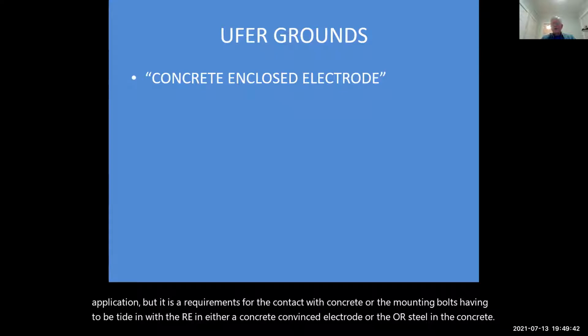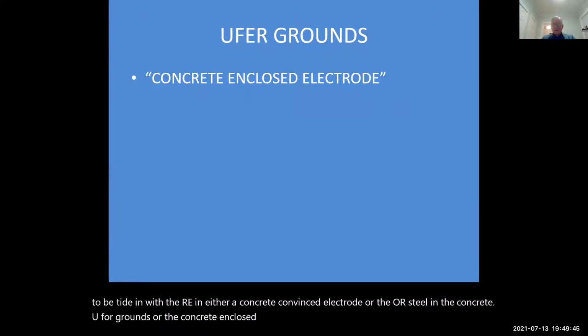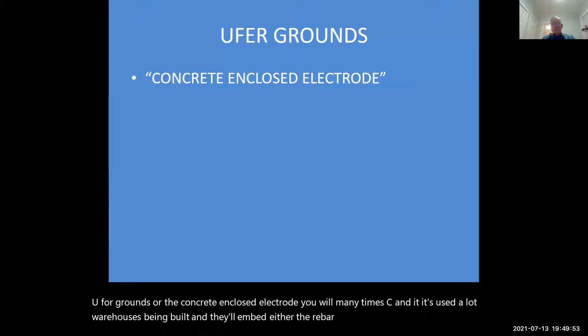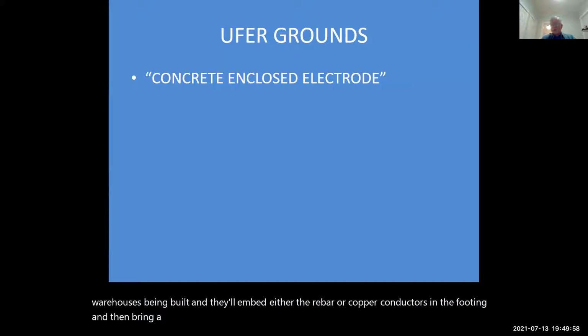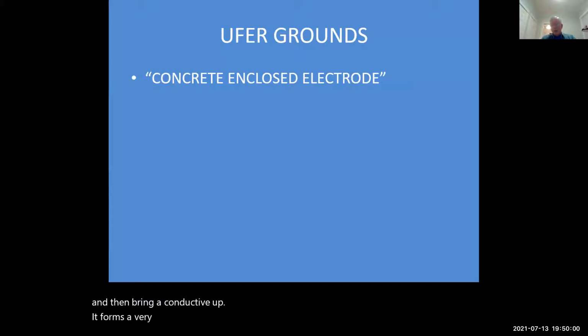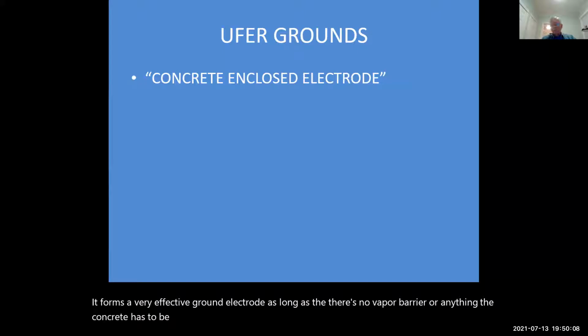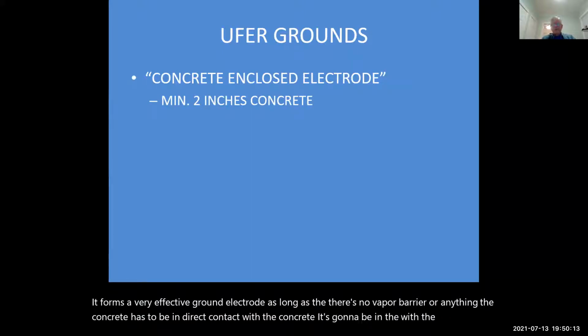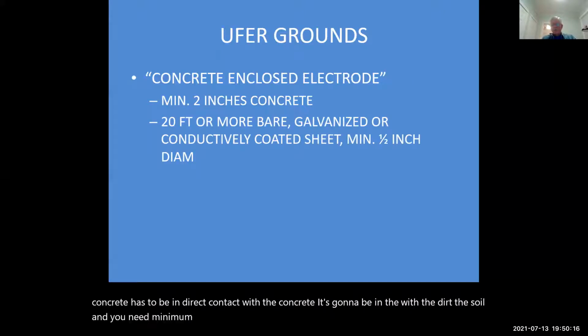UFER grounds, or the concrete enclosed electrode, you will many times see, and it's used a lot where a house is being built and they'll embed either the rebar or copper conductors in the footing and then bring a conductor up. It forms a very effective ground electrode as long as there's no vapor barrier or anything. The concrete has to be in direct contact with the soil, the dirt, and you need minimum 2 inches of concrete around the conductive part, whether it's rebar or copper.